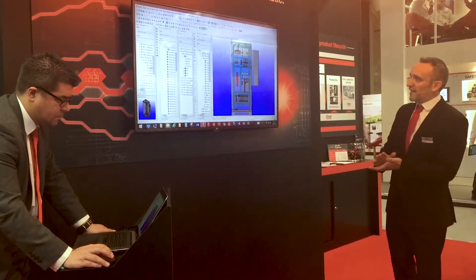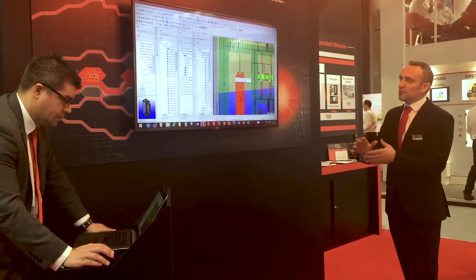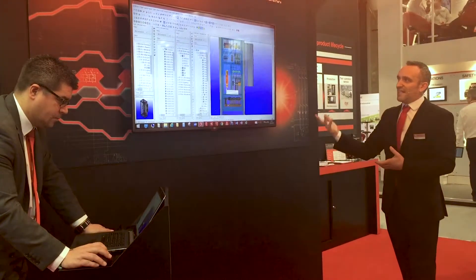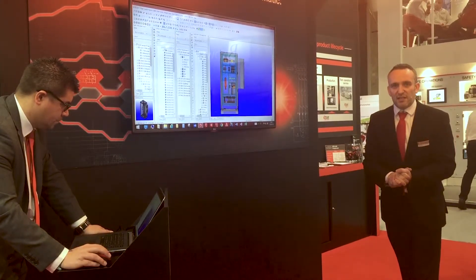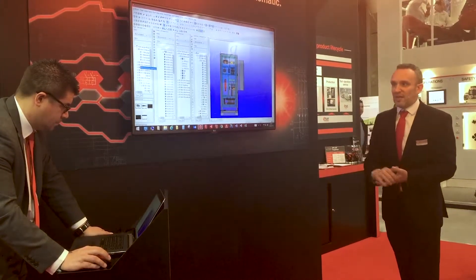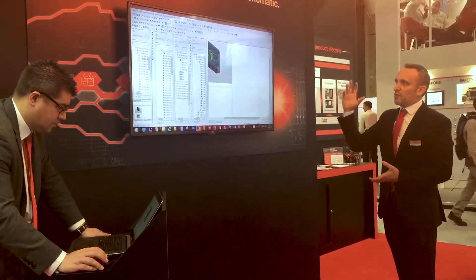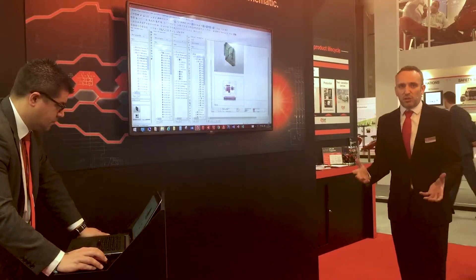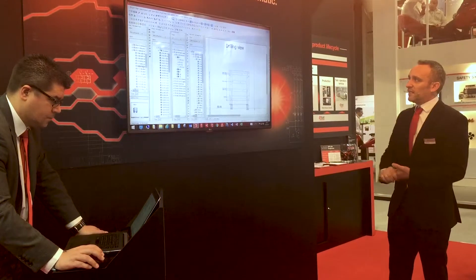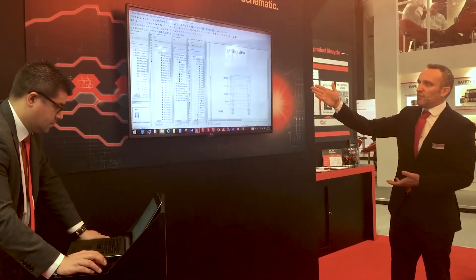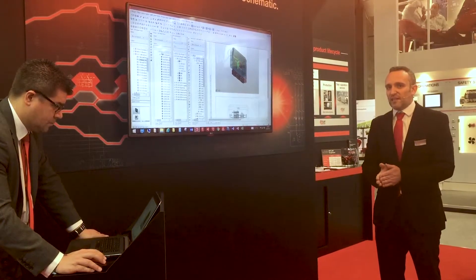What we can update then is all the drill patterns and cut-out patterns for the panel as well. So very quickly and easily, we can not only make sure our design is correct and everything fits correctly, but also have accurate wire lengths, good accurate drilling and cut-out patterns, and produce solid information for the shop floor to make sure the production of this panel is built correctly. We've just created a simple drill view, all by dropping the components down onto the actual panel itself.